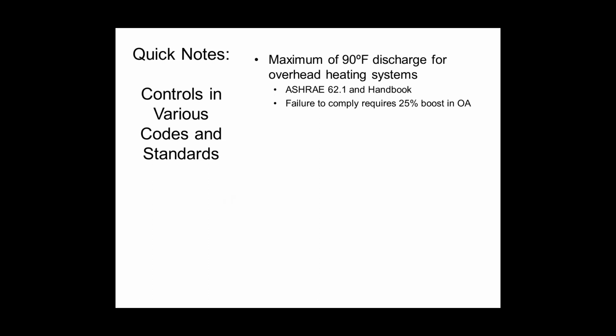Basically, what ends up happening is, if you have an overhead heating system, like you'd have in an office with a VAV or something like that, you cannot have the discharge air temperature be any more than 15 degrees above the space temperature. If you do that, a bunch of rules kick in. The big major rule in ASHRAE 62 requires you to add 25% outside air to whatever CFM you're supposed to bring into the building. It gives it a ventilation effectiveness of 0.8 instead of the default of 1.0 like overhead cooling would have, which the math ends up telling you means you have to bring in 25% more outside air.